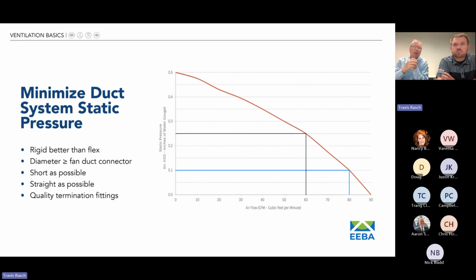So this graph you see here is a graph of a typical 80 CFM bath fan. On the vertical axis, we have static pressure, and on the horizontal axis, airflow. If you look at the blue horizontal line, that's at 1/10 inch of static pressure. That's a very, very good level, a good duct installation. I draw a blue line there because for bath fans and range hoods, that's the standard rating point. If you pull that across, go to the red fan curve of this fan, and drop it down, you'll see why it's rated at 80 CFM. At 1/10 inch, it'll move 80.